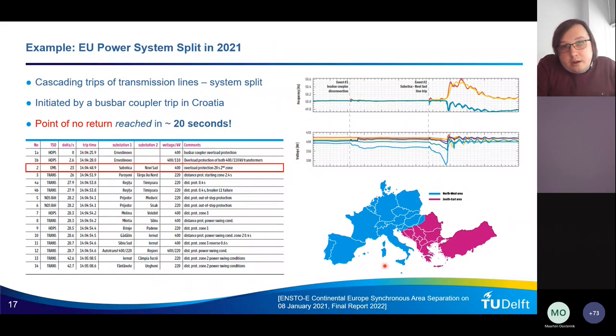To give you a flavor of why this may be possible, we can look at a real incident in 2021 that happened in continental Europe, in the interconnected power grids of Europe. Here you see the map. There were cascading trips of transmission lines that led the interconnected power grids in Europe that you see here to split in two areas, one here in the east and one in the west. By splitting the system, it means that all the power lines, the interconnectors, were disconnected along this line. The system typically operates at one unique frequency, that is 50 hertz. And then you have two frequency levels, one in each area.